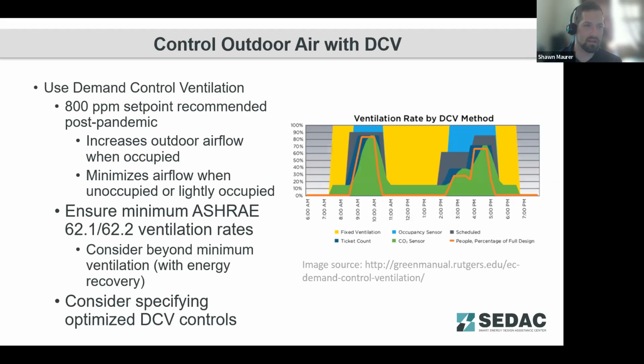Controlling outdoor air. For demand control ventilation, typical standards in the past are about 1,100 parts per million. We see slightly higher set points now, about 800 parts per million, to increase ventilation just due to the pandemic and people's concerns about indoor air quality. Really, if you can ensure that your buildings are actually meeting their ASHRAE 62.1 ventilation rates, or 62.2 for residential buildings, by and large, they're going to have good indoor air quality.